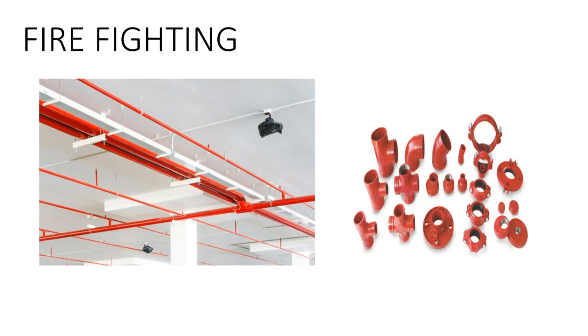As you can see in this first picture, we have firefighting pipes. The firefighting pipes could be GI pipe or black steel pipe, depending on your project specification or client requirement. For underground, the pipe will be HDPE pressure pipe, which can withstand at least 16 bar pressure.